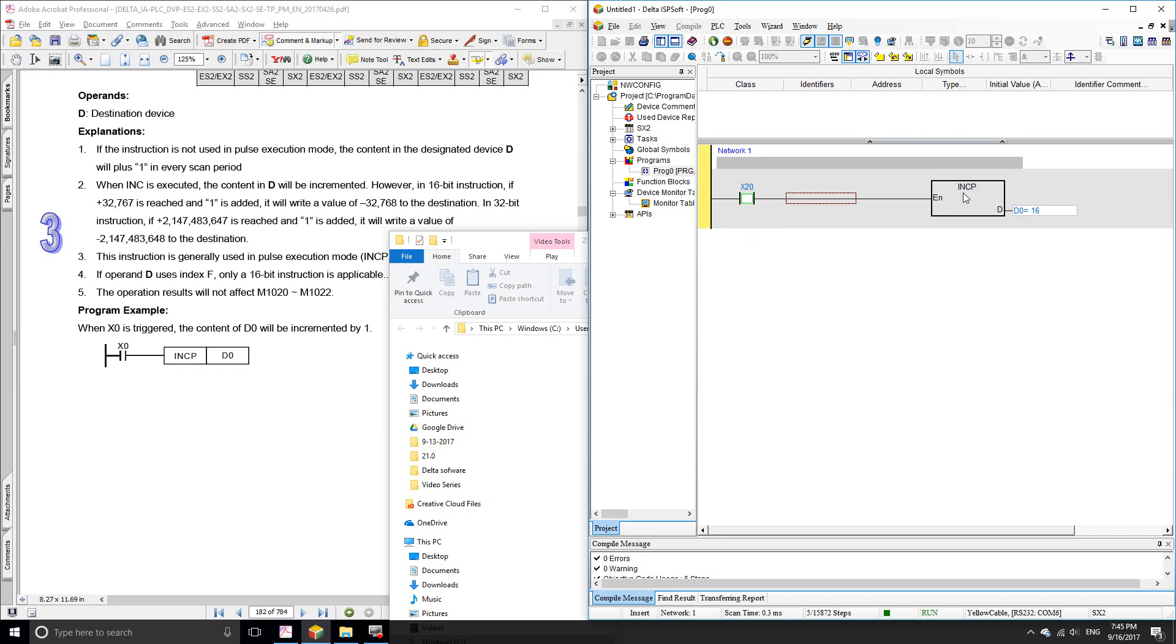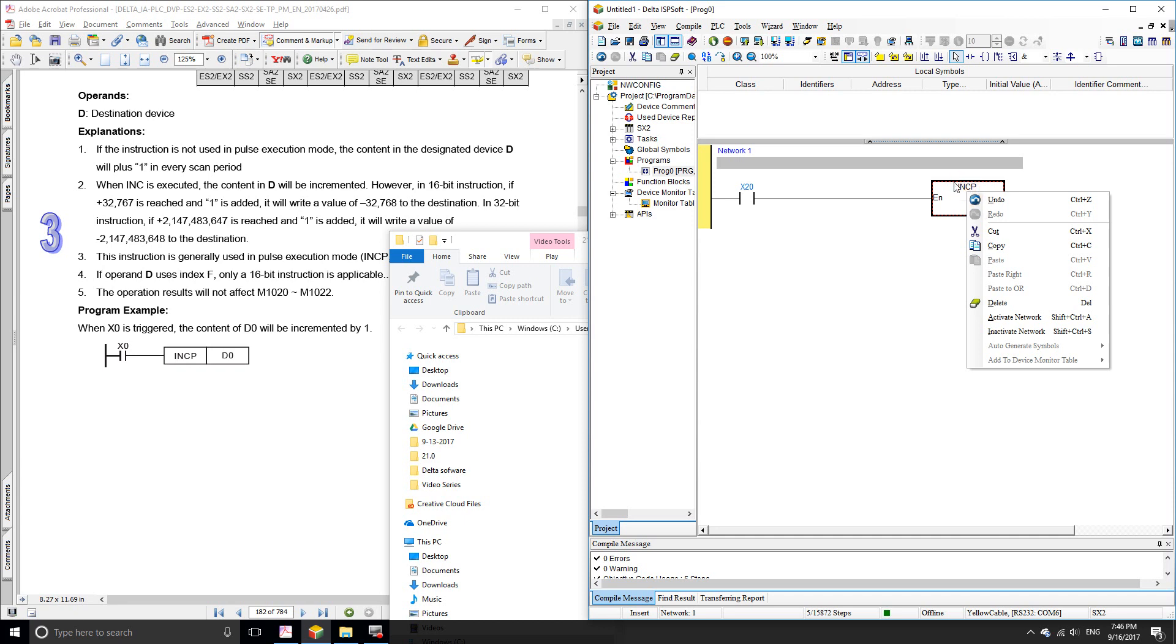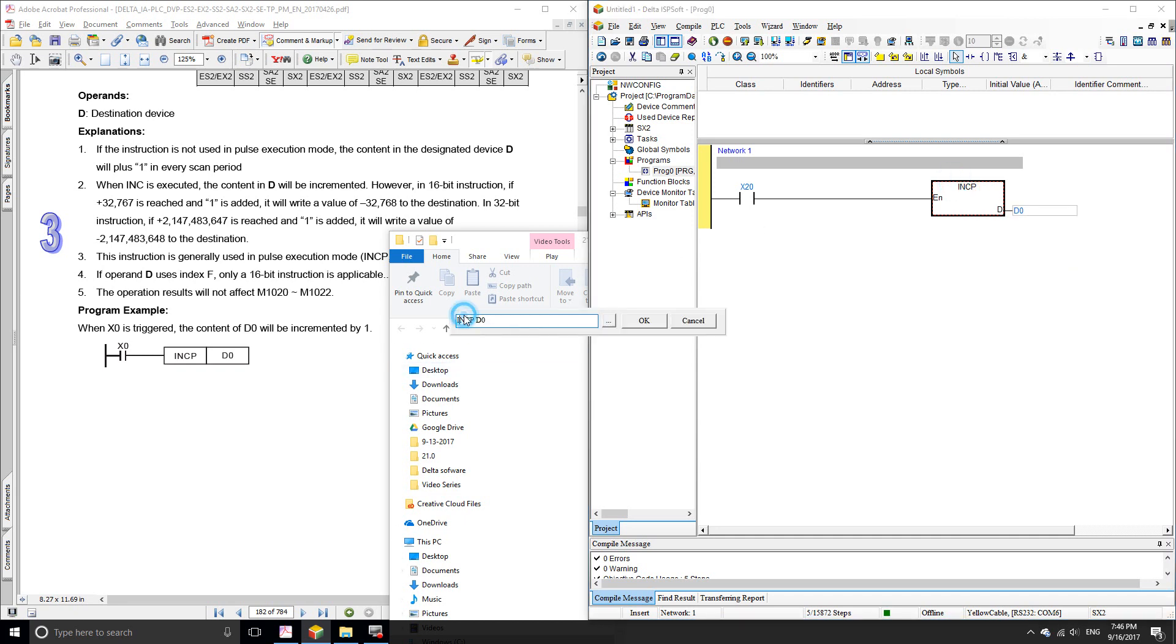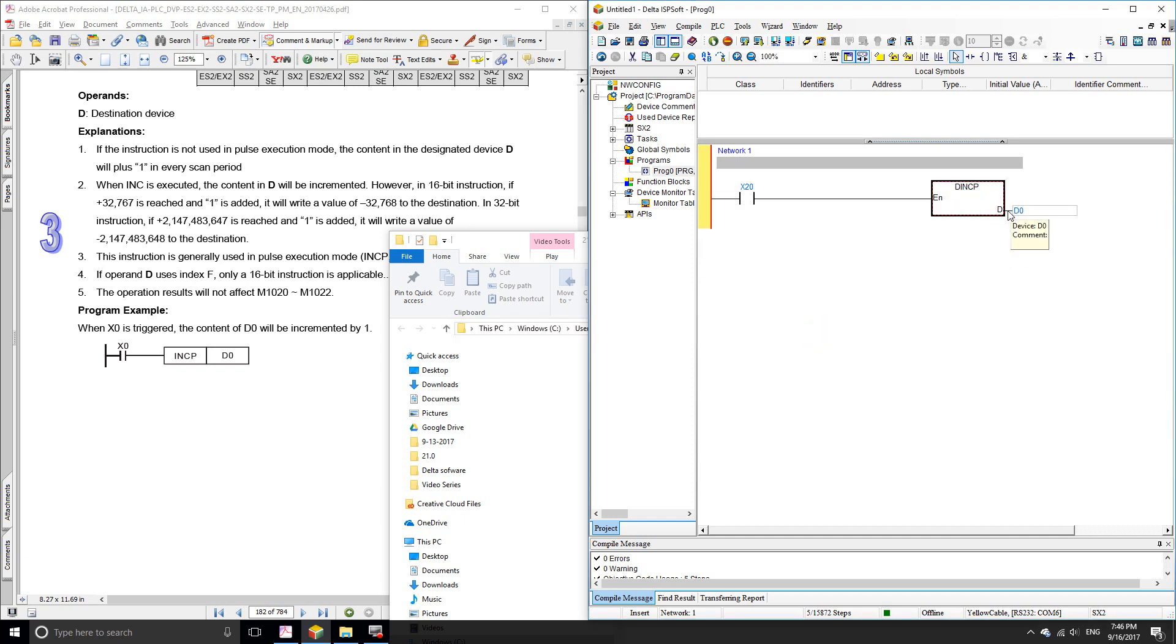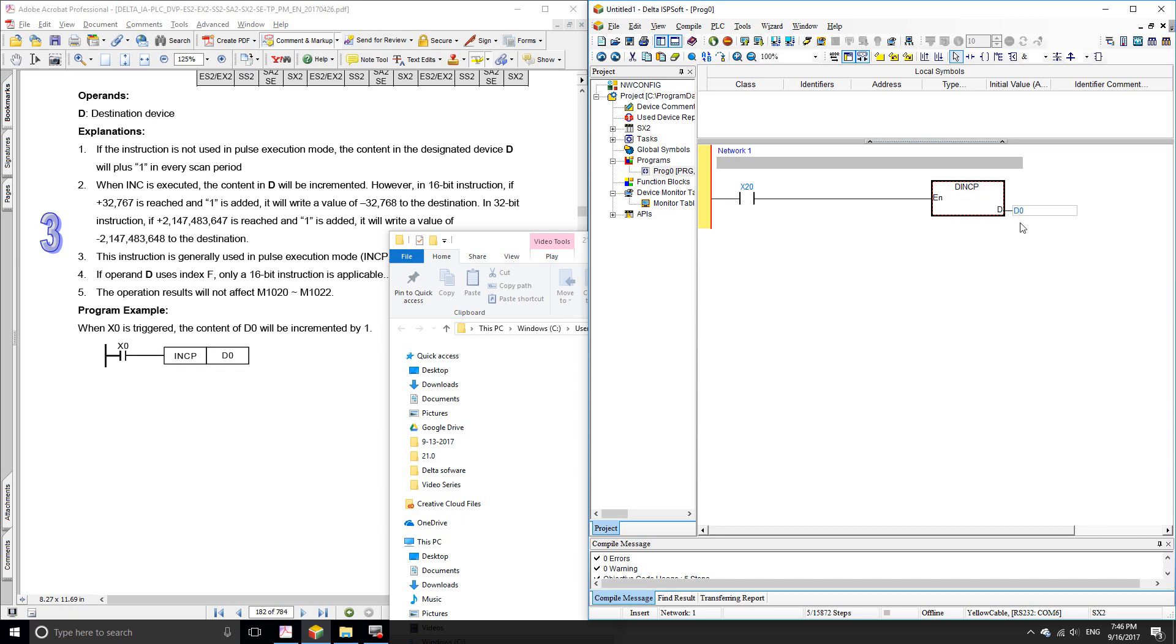You need to be aware of that. Also, if you're going to be using larger numbers, remember to add the D at the beginning of the instruction so that you can work with 32-bit numbers. Remember once again that 32-bit numbers use two consecutive registers. One register only holds 16-bit numbers, so to make a 32-bit value it uses two. If you assign D0, then it's also going to use D1 to store the value. Remember, don't use D1 because it's being used by this function, otherwise you're going to have problems.